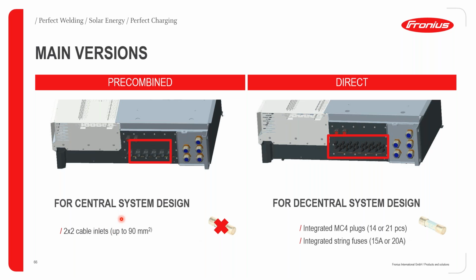So the central design will be capable of taking up to 90 mm DC cables. In this setup, we are not going to require the DC string fuses, because the DC combiner box should be handling the string protection with the appropriate fuses. When you talk about the direct version, whereby we are connecting the strings directly to the inverter, we can see we have quite a number of MC4 plugs provided for the inverter. There will be between 14 to 21, depending on the version of the inverter that you are going to take. Also, the string fuses will be integrated, either 15 or 20 amps per string.